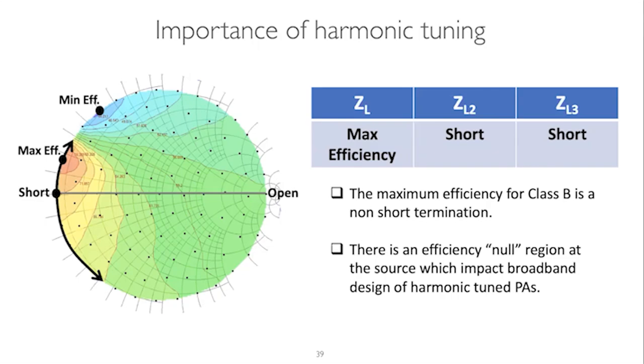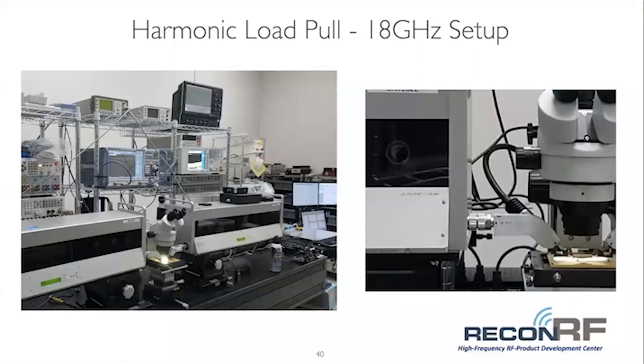So this really shows you how careful you have to be about where you set those impedances. In this example, if you set it to 50 ohms versus a short, you'd have a 6 to 7 point difference. But if you set it to a short and open, you'd probably get a 2-3 or even a 1 point difference. This really shows how important it is to characterize the harmonic performance of your device. So a lot of people will say, well, okay, this is nice and dandy.